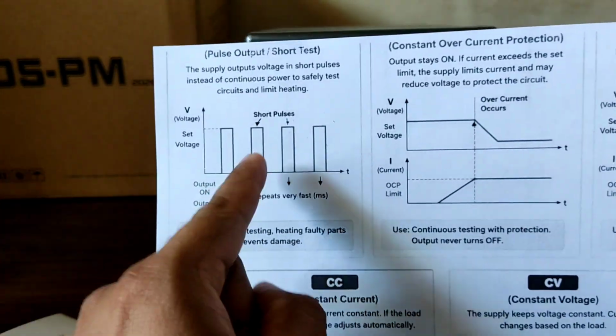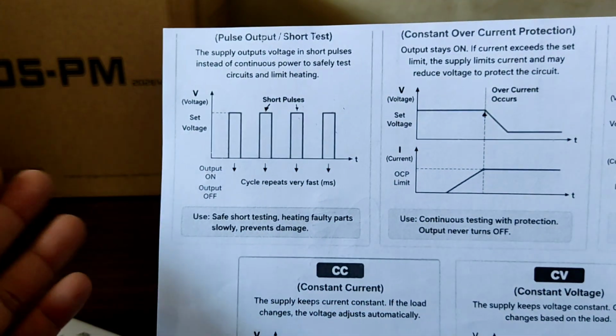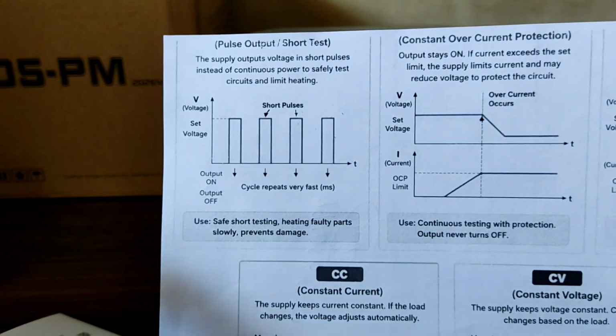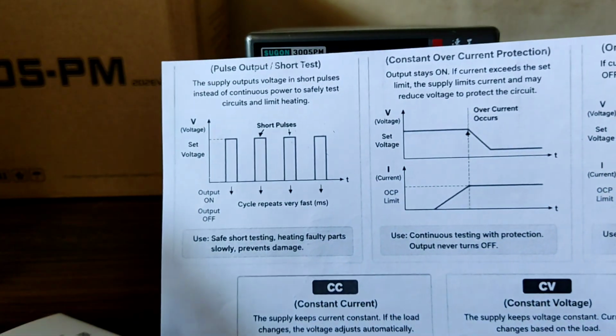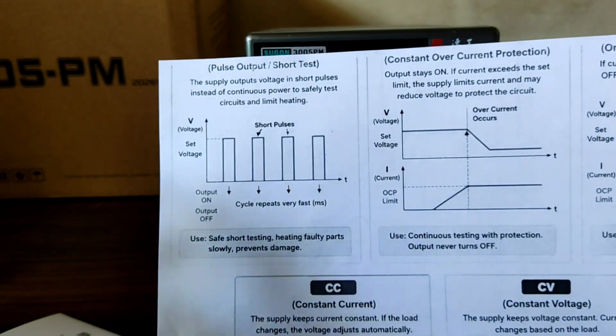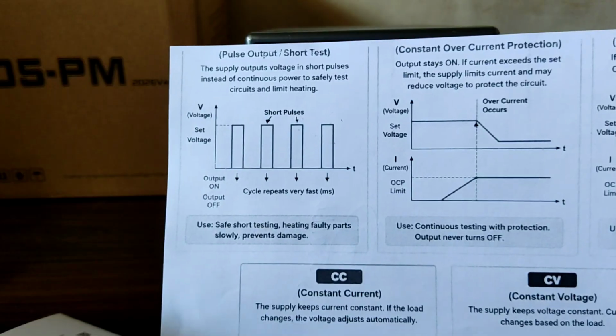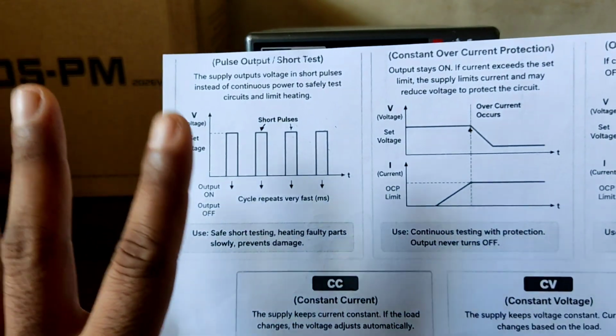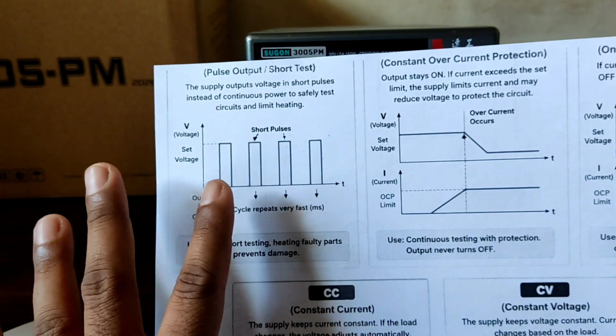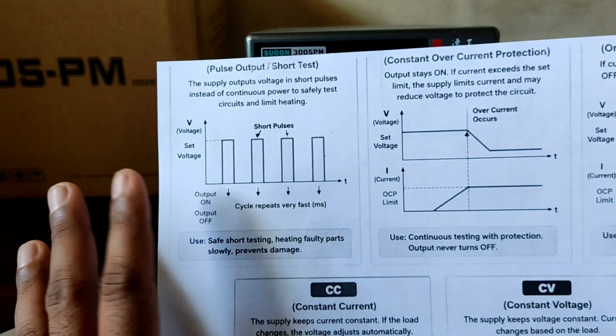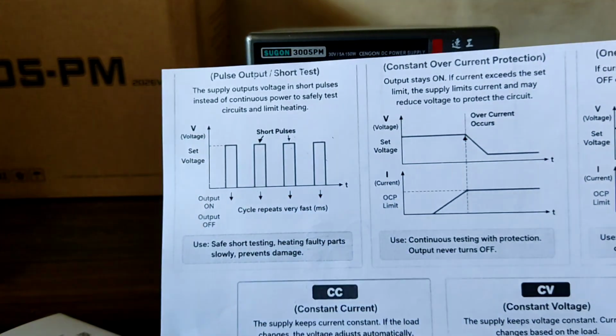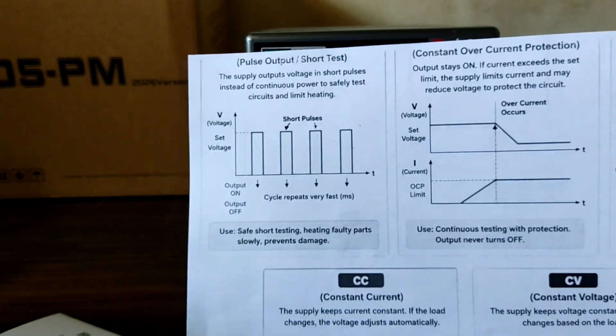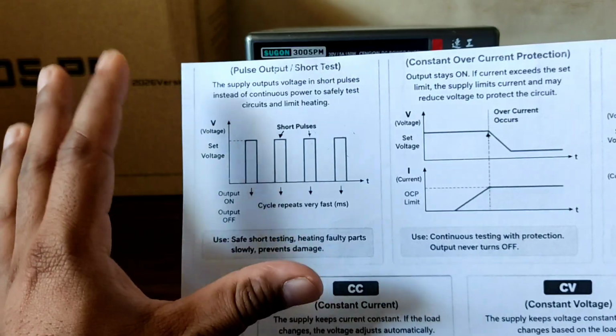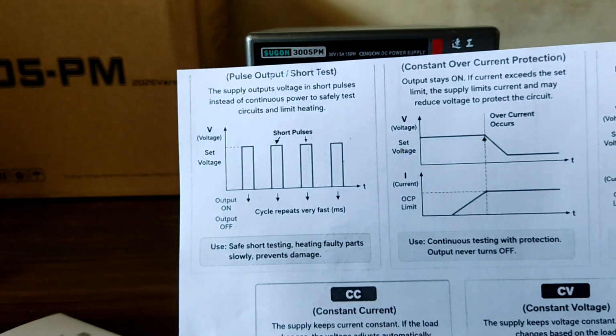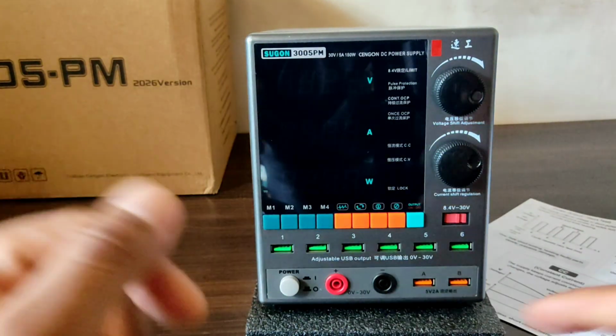So it will give pulses of voltage, not continuous voltage. Then the chip or whatever the faulty item is slowly gets hot, and that time I can observe and troubleshoot. This is only for sensitive working with sections like processor and graphic card, and if you don't know the condition of the board you're repairing, for safety purpose they gave this. This is not mostly used, but it's there for certain conditions.